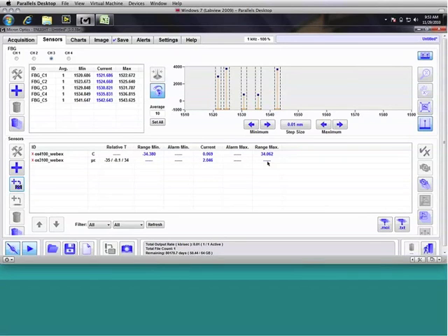And then also that FBG is going to have wavelength shifts induced just because of changes in operating temperature. And so as we establish spectral bins on this graph on the upper right side of the Sensors tab, we need to make sure that we're provisioning for both those shifts that are going to be seen by changes in ambient temperature, as well as shifts that are going to be seen by the desired measurement quantity, such as strain or temperature.